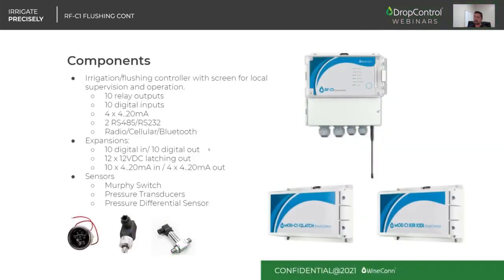So in order to be able to control all the components, we do have our main RF C1 controller unit that already comes with multiple outputs to control different devices, such as pumps or valves. It has multiple digital inputs to read flow meters or any on-off signal. It has 4 to 20 milliamp inputs for level transducers, pressure transducers, pH, EC, etc. It has 2 serial inputs in order to read different VFD variables or energy meters if you would like to keep track of all the electrical variables.